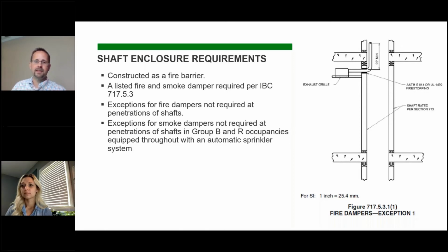The other thing to think about is how you are going to control that fan. If your exhaust on all these floors is constant, it's pretty easy. You can do a constant volume fan, but there are a lot of applications, and we talk about dryers in here, where those are not a constant airflow. And so you have to keep that continuous upward airflow no matter what. So there are more complex control systems that we're not going to get into here that need to be thought through when you're using this exception. Again, there are a lot of applications where this can be used and where this is very valuable, but it's not for every application. And there are some things that need to be thought through before implementing it on a project.